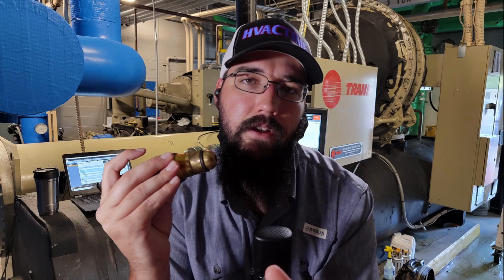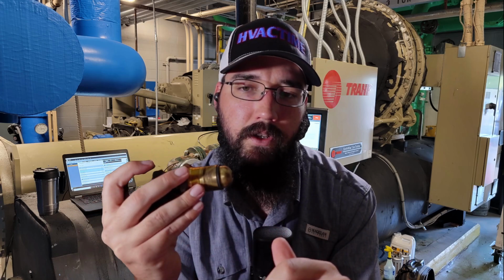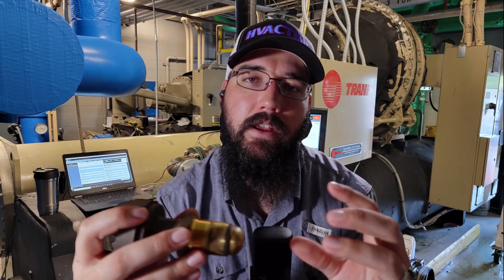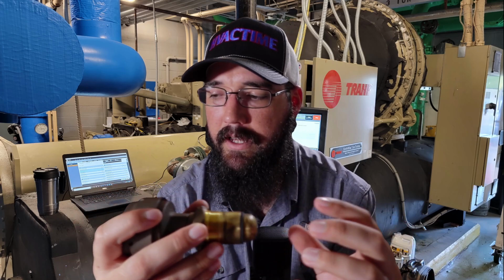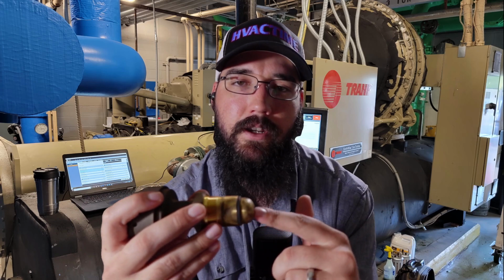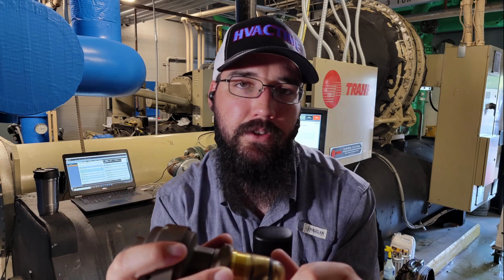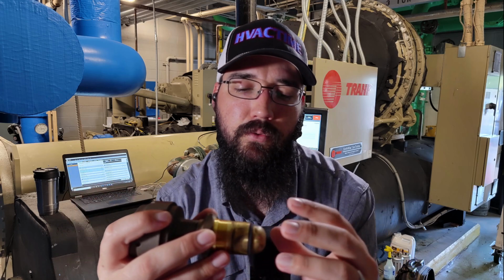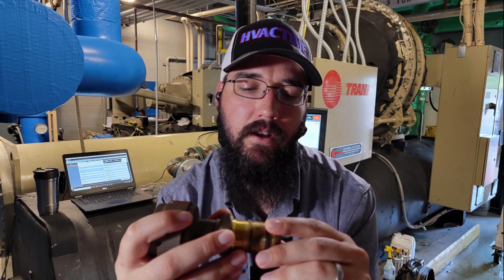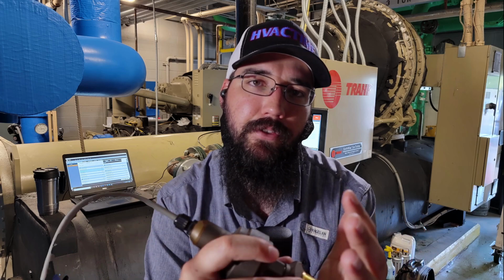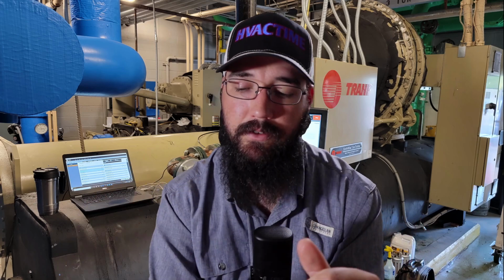So that's another common mistake when doing a body change like that, or a head change. If you're going to test this or do any kind of calibration checks before you put it in, make sure that it's in the fully open position before installing it into the body. If you have it fully extended, you will end up bottoming it out trying to thread it in, and then you will end up tearing the threads up because it went too far. This valve will extend that plunger further than the body has depth to go. Very easy, but very common mistake that I have seen happen.